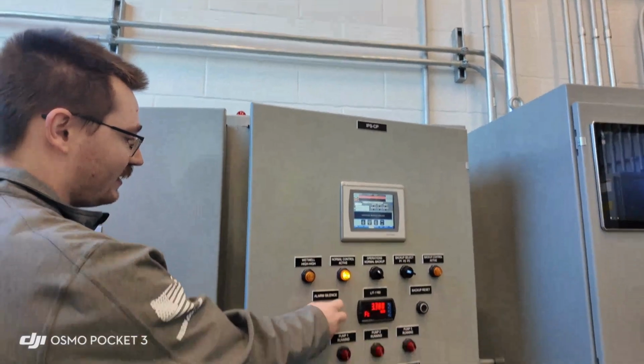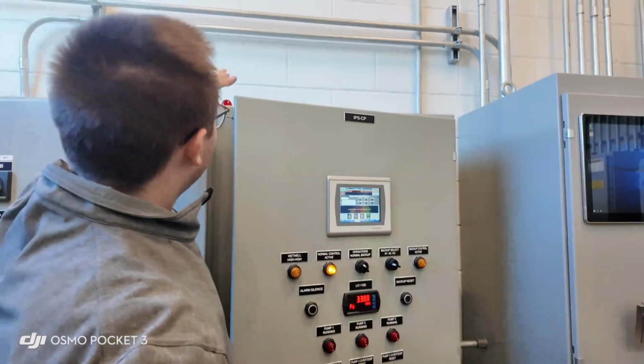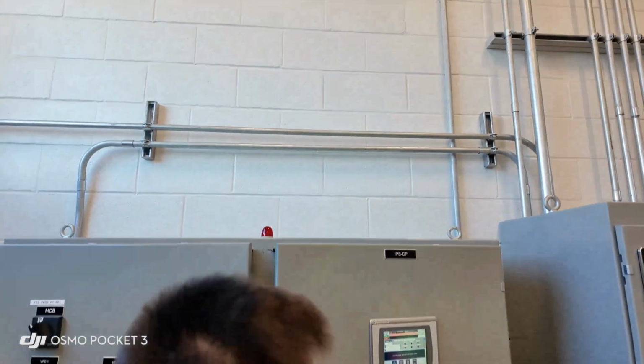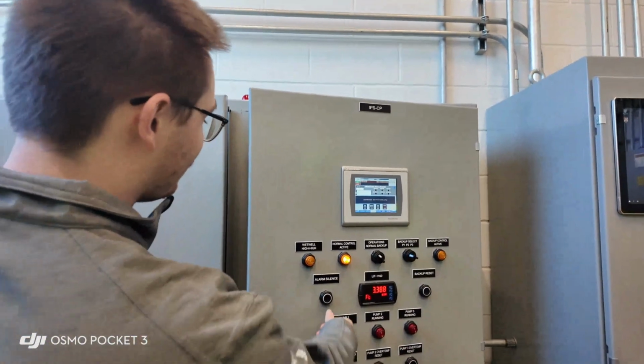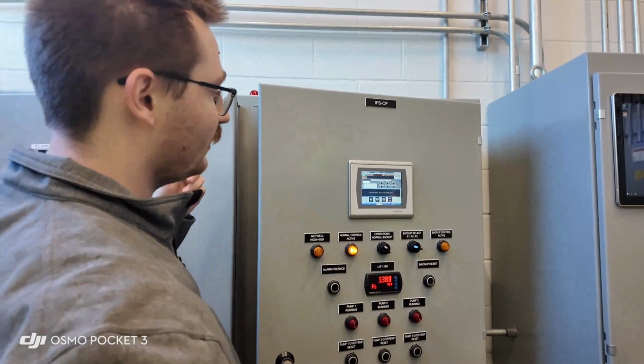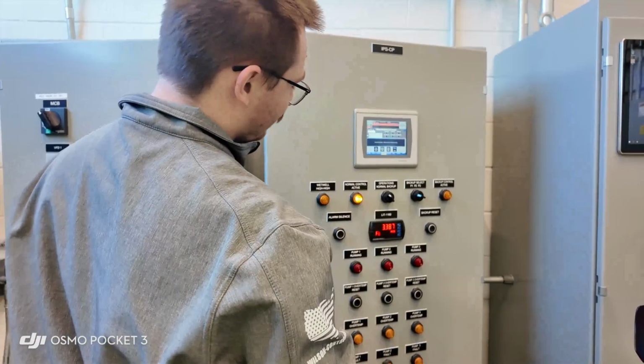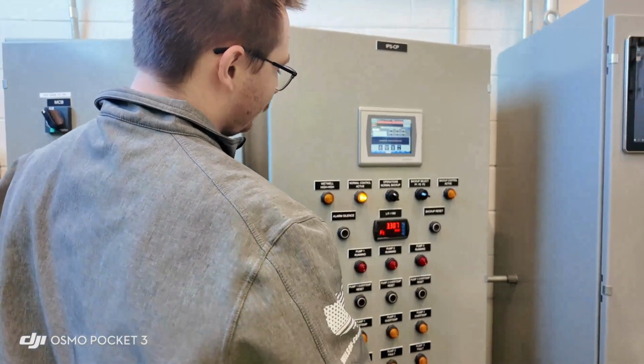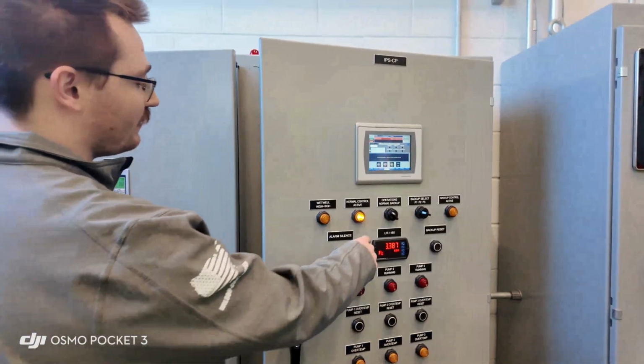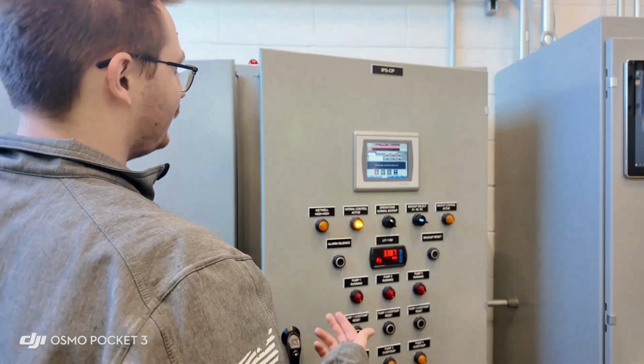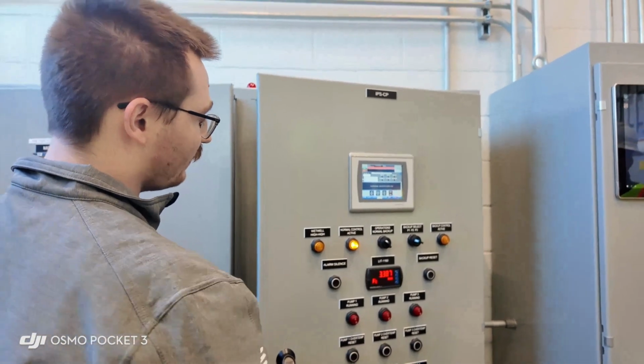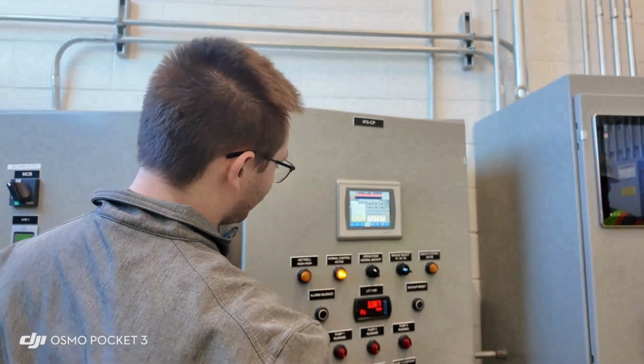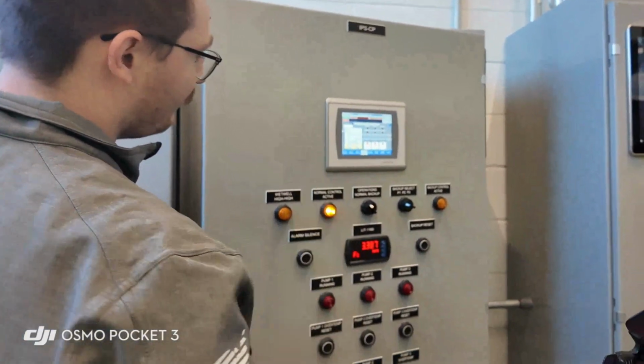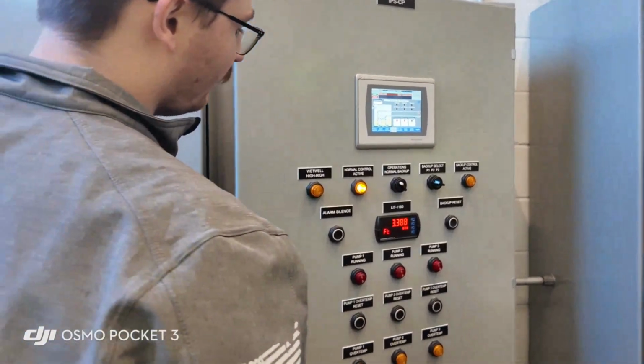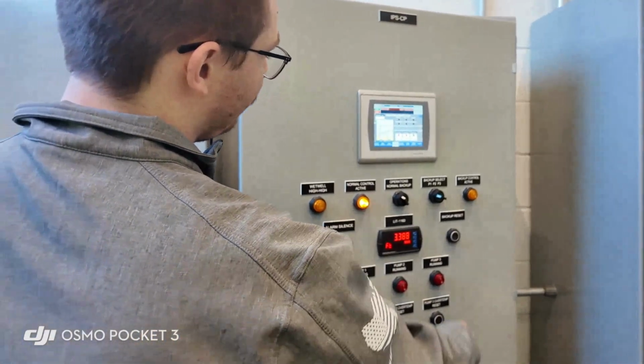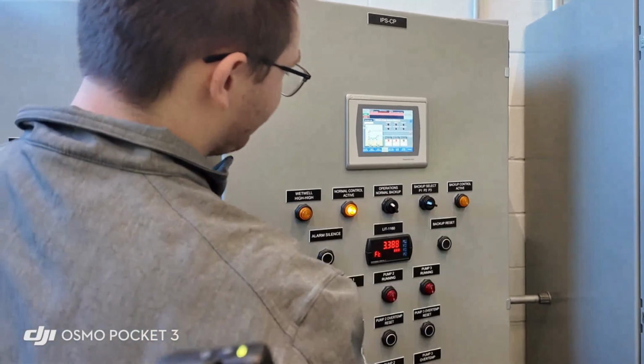We have an alarm silence. If there's any common alarm, we have a strobe light up here. So the strobe will flash, and then the horn will go off. You can silence the horn, and the strobe will still be going. We have a digital display for the wet well level, pretty much an output from the PLC that goes directly to it. The wet well level goes into the PLC, and we're just outputting over here, so it matches up to what's on the screen. The screen does round up to 0.1, and then this is the backup reset to reset back to normal operations.